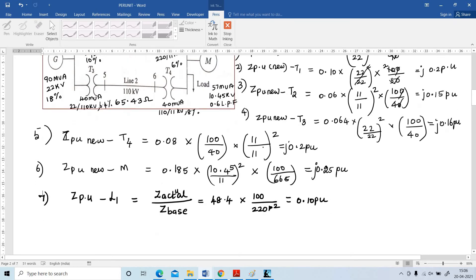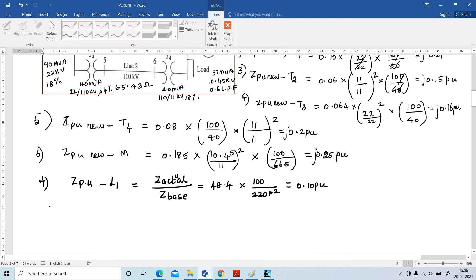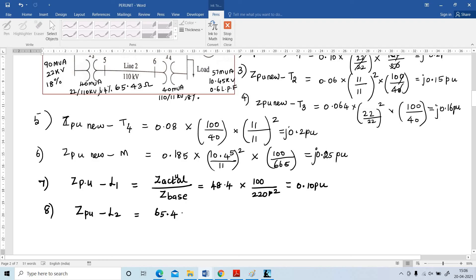In the same manner, find ZPU for line 2. Z_actual = 65.43 ohm. Voltage in section for line 2 is 110 kV. Z_base = (110)² / 100 = 121 ohm. ZPU = 65.43 / 121 = 0.54 per unit.